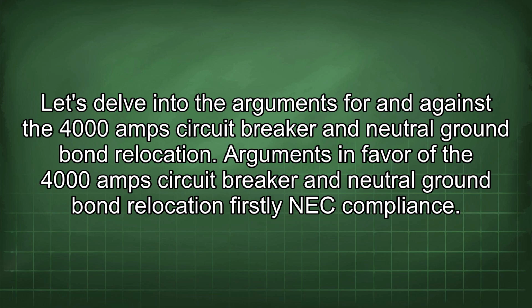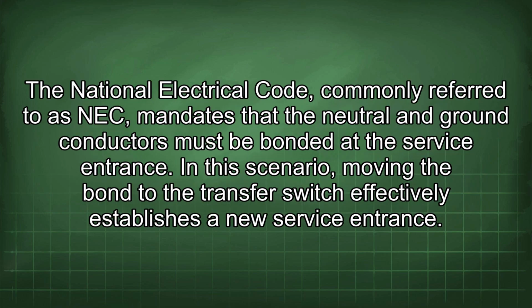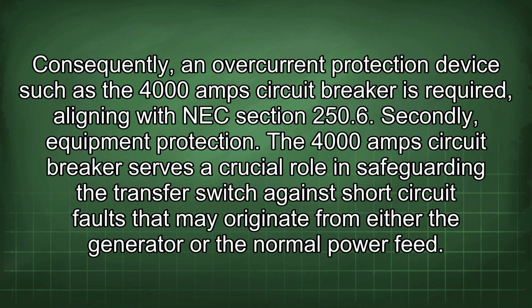Arguments in favor of the 4000 amp circuit breaker and neutral ground bond relocation. Firstly, NEC compliance. The National Electrical Code, commonly referred to as NEC, mandates that the neutral and ground conductors must be bonded at the service entrance. In this scenario, moving the bond to the transfer switch effectively establishes a new service entrance. Consequently, an overcurrent protection device such as the 4000 amp circuit breaker is required, aligning with NEC section 250.6.